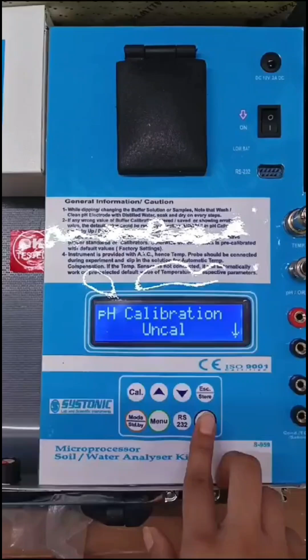and this sample holder is for turbidity. Now we will turn it on through this. First we'll check the pH. For this you have to go to cal and to pH, press enter, and the first thing you have to do is uncal it. So press enter.